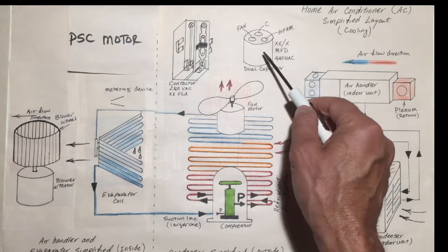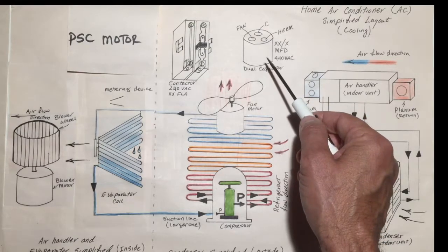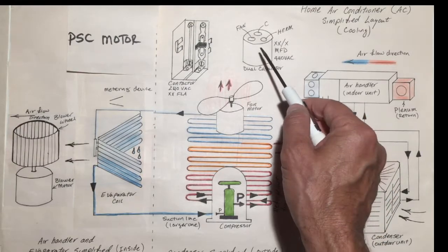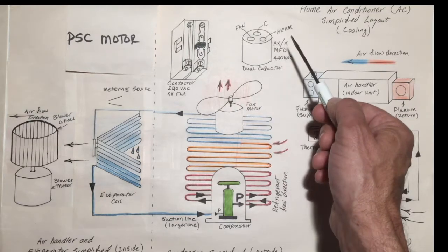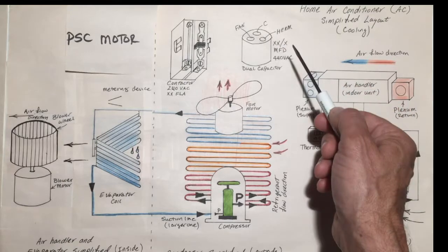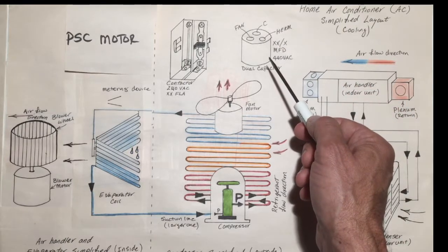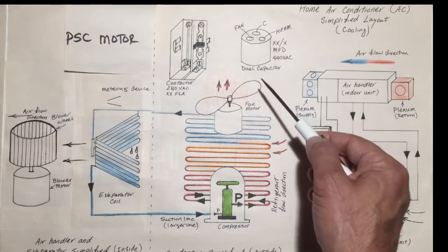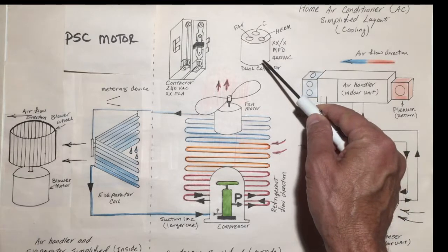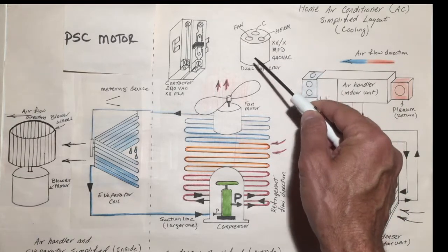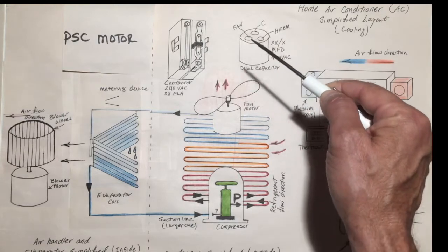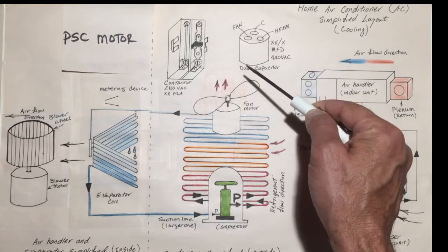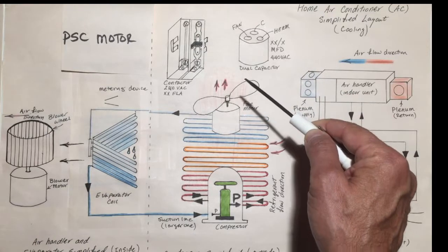Historically, I've noticed that these caps last anywhere between 4 to 5 years. Now, the cost of the cap is fairly inexpensive, anywhere between $10 to $15. But what is costly is the labor that's associated with identifying the cap, having the proper license, and having the proper knowledge to identify and replace the cap.